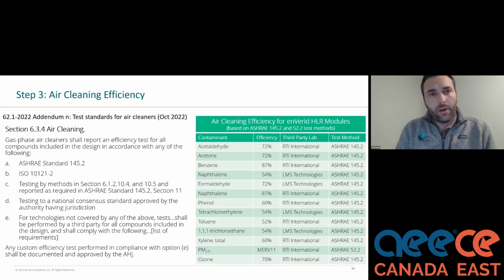Air cleaning efficiency. This is where selecting a product becomes very important. This is why we're proud to be partnered with organizations like Odell, who have kind of vetted these things out with us and said, yep, this is a product worth representing. ASHRAE has given us specific methodologies for gas phase air cleaners to test these products and get everyone on a level playing field. One of these testing standards, how we test our devices, is ASHRAE standard 145.2. It's a single pass gaseous contaminant removal test, which ensures no byproducts. And we use our end of life efficiencies in the calculator to ensure that day one, the indoor air quality in these buildings is phenomenal.